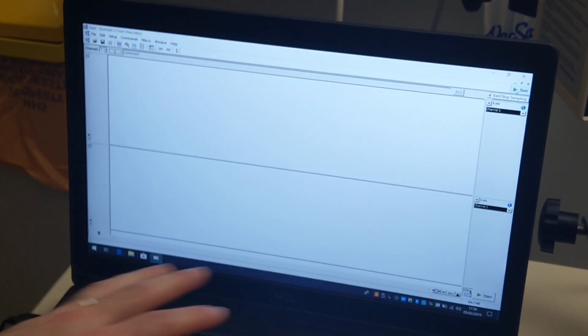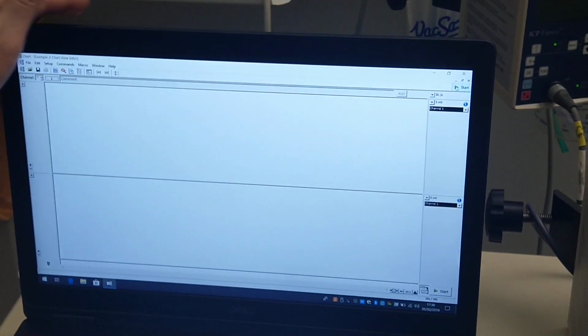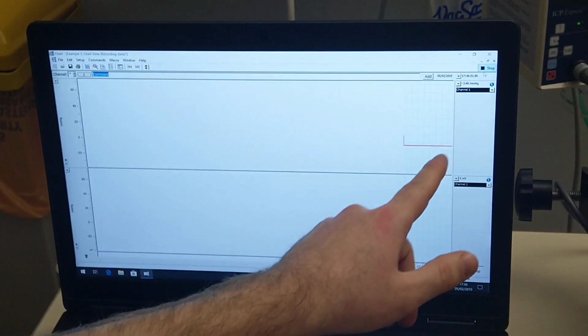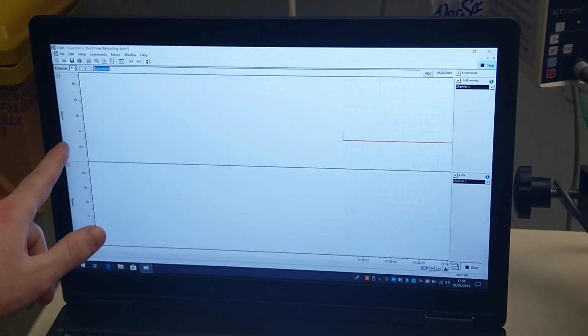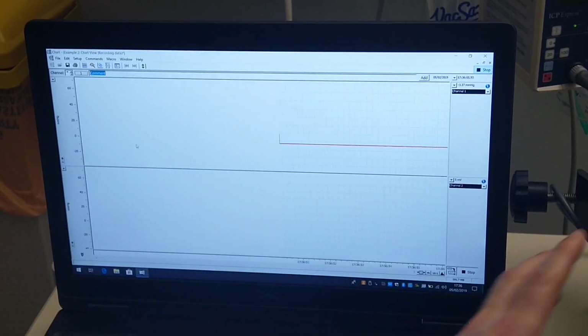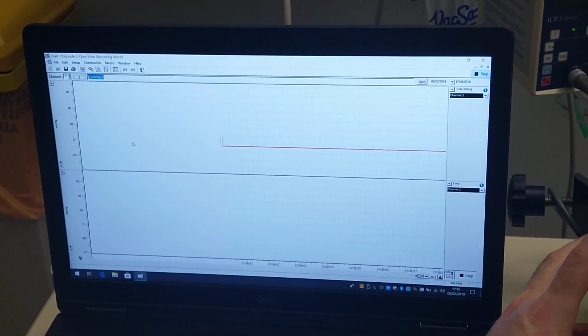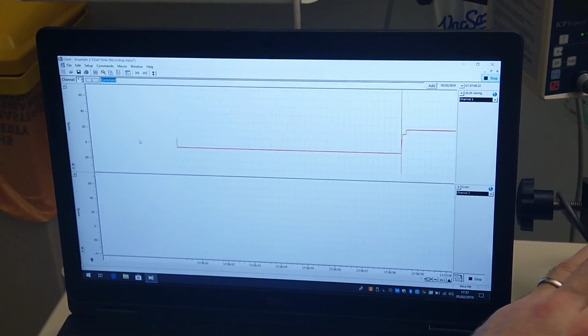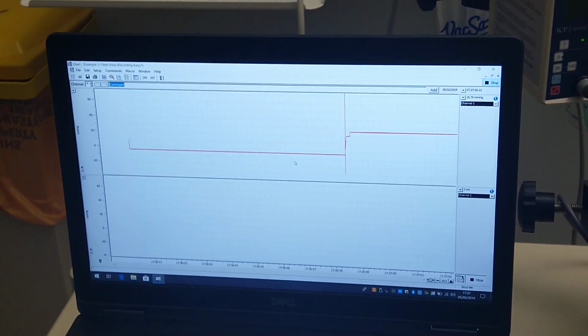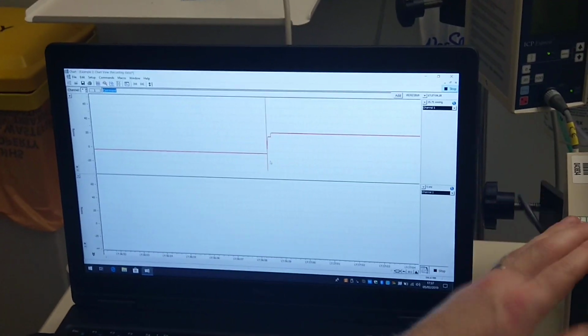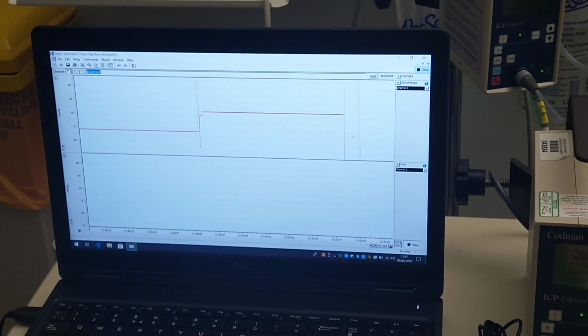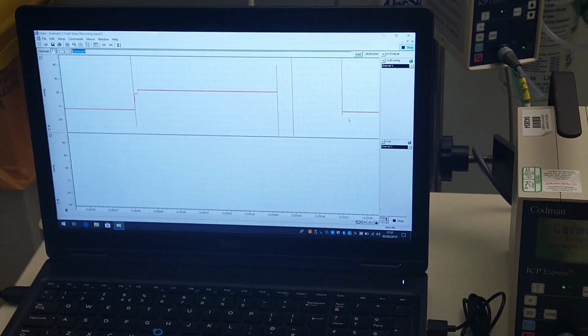Now what we're going to do is press Start here. We need to zero the ICP box to the computer, so you need a trace to be able to see the zero. I've made the trace start, and you can see that trace is running along near 0. Then we turn on the ICP Codman box. This is the one that's attached to the ICP computer, so don't use the one that comes to the patient, use the one that's attached to the box. In a second, it should start to show a trace again.